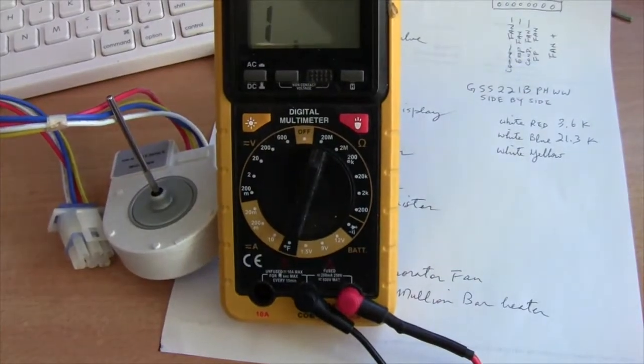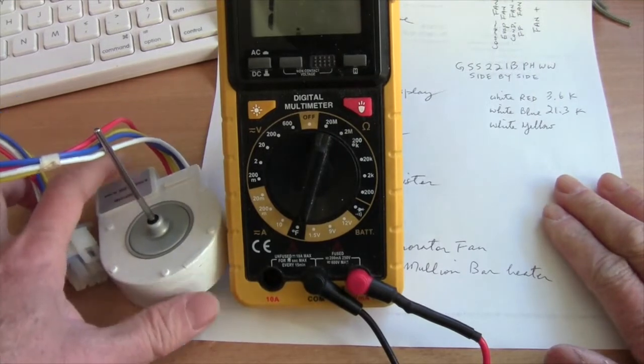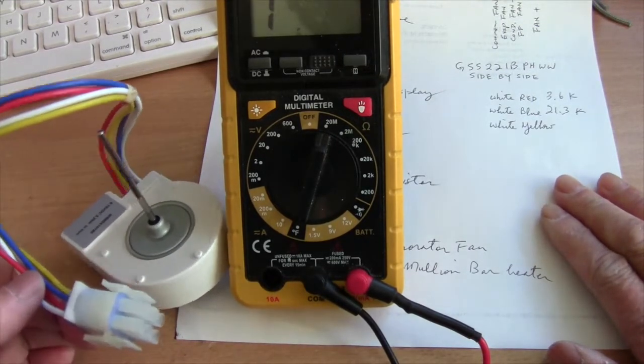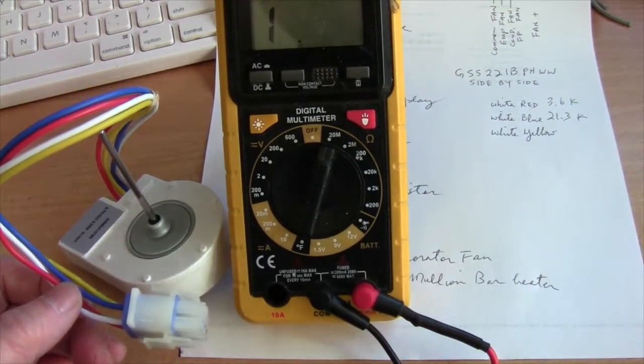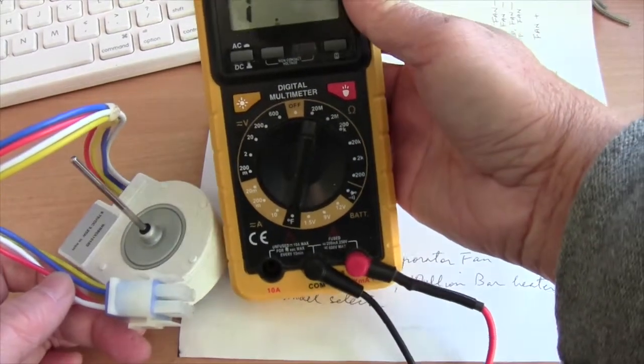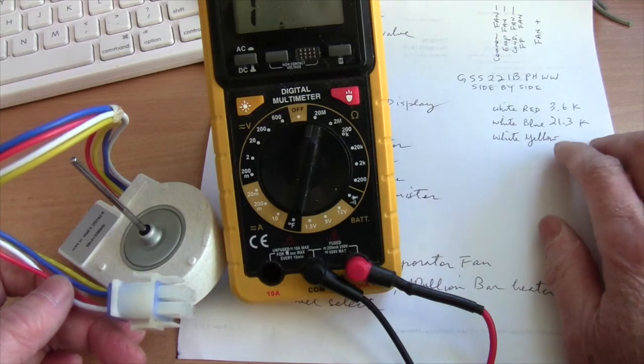So I did that for some of the components. And also for the evaporator fan, I checked out the resistance between the different wires. So if you have a fan motor, you don't know if it's good or bad, if it's shorted out or what, then you can take a look at what I wrote down.